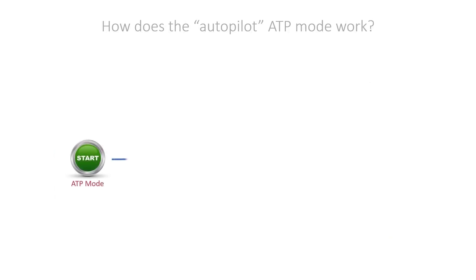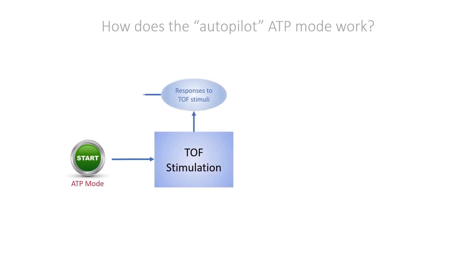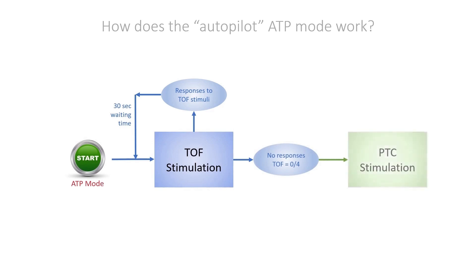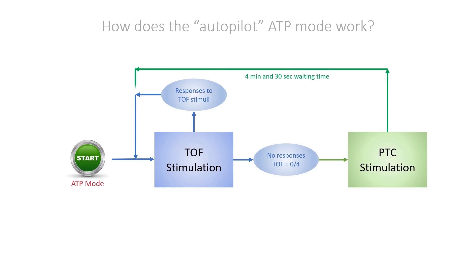The TOF scan pilots the choice of TOF or PTC according to the patient's response. A TOF will be applied every 30 seconds as long as the TOF count has one answer. When there are no more answers to the TOF count, the PTC will automatically start. 4 minutes and 30 seconds later a new TOF will be delivered, and if there are no responses — for example a TOF count of 0 — a PTC will start. This will continue until the TOF responses are back, then the device will only do the TOF every 30 seconds.